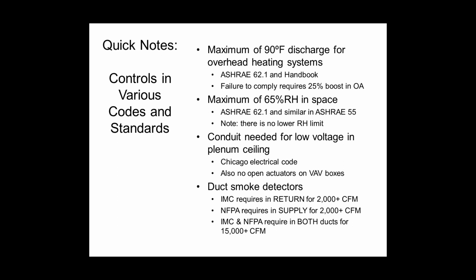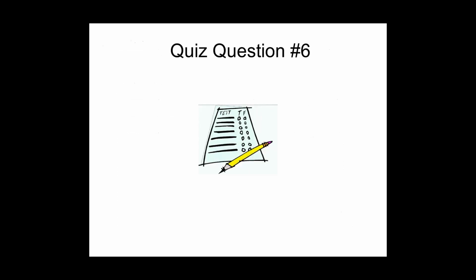And then both of those codes require dual monitoring, return and supply, anytime it's above 15,000 CFM. So plan on providing at least one smoke detector, if not two, on every air handler. It's going to come up a lot.